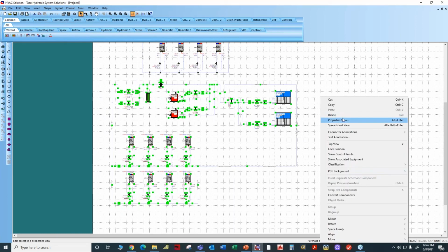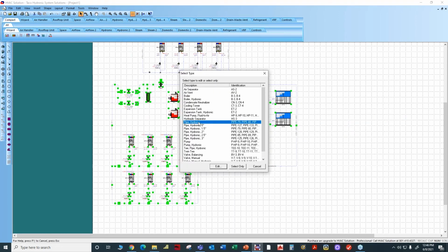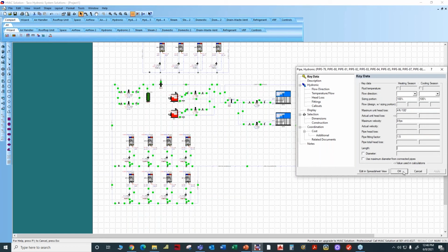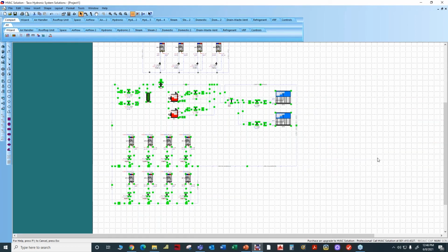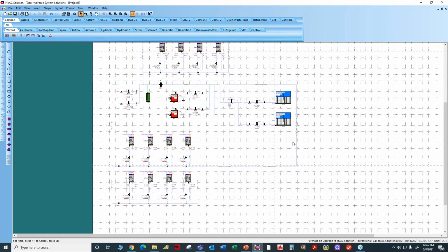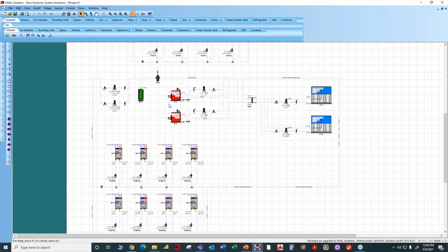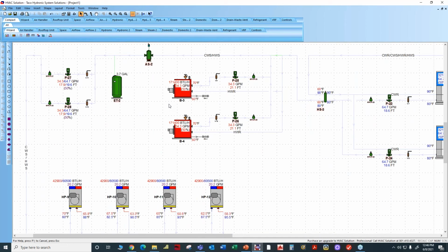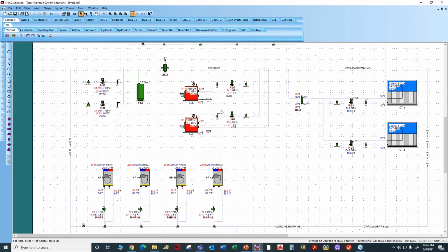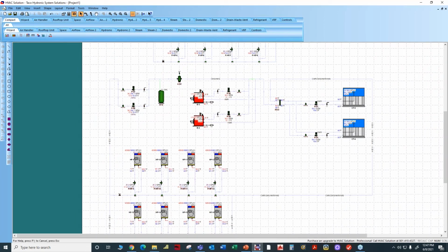I would suggest heat pump system wise, this design is probably a little more traditional than the one where you're using a heat pump for generation of the fluid. Yeah, this is the more common one that we see out there, although we think that the air to water heat pump will gain in popularity because basically it does not use a fossil fuel. It's an all electric system, where this system implies that we're using either one of the 3 major fossil fuels: natural gas, propane, or oil in this particular case here. So we'll do a quick equipment selection.